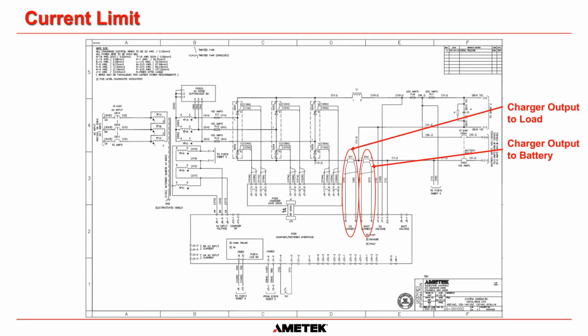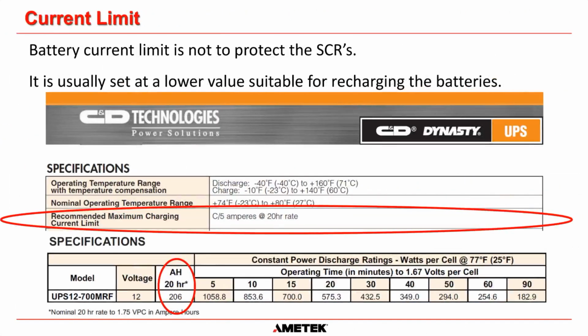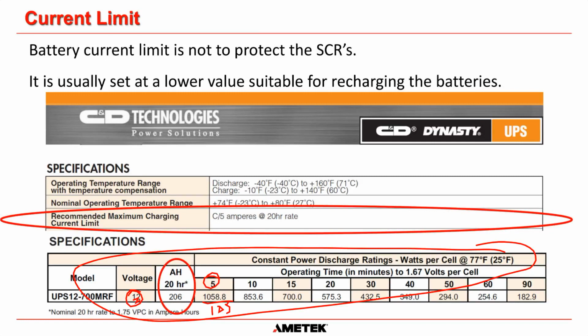The battery current limit is dependent on what the battery manufacturer tells us. And this is a contentious issue, in my opinion. You know, if you designed your battery, like this battery here, for example, this is a C&D battery, okay? And it's saying here, this is constant power. So for 5 minutes at 12 volts, it's saying that you can get 1058 watts. Okay, so let's say that's 10 volts just for ease. You would divide 1058 by 10, that would give you 105 amps. So this table here is saying this battery is quite easily going to give you 105 amps without any issues.